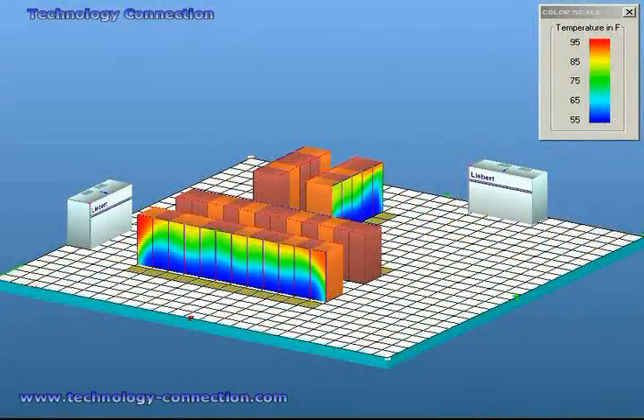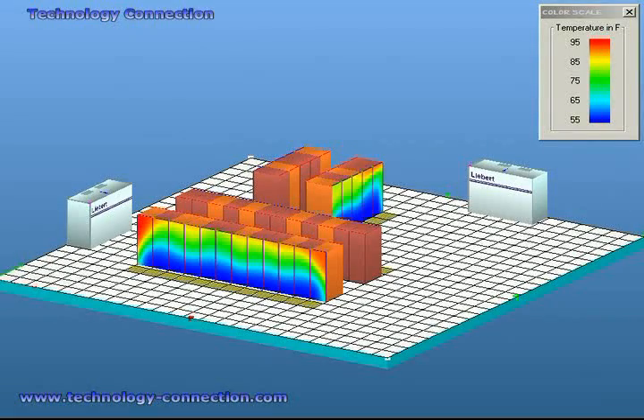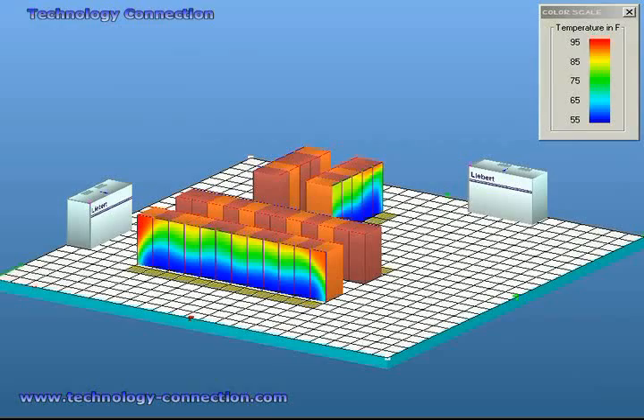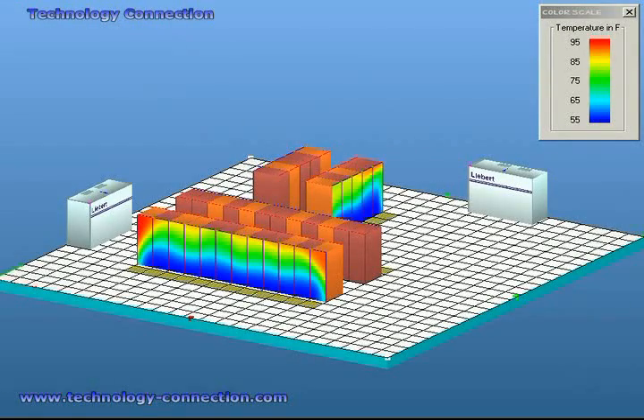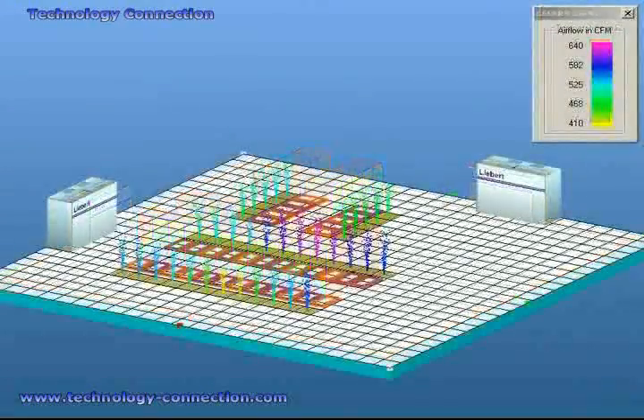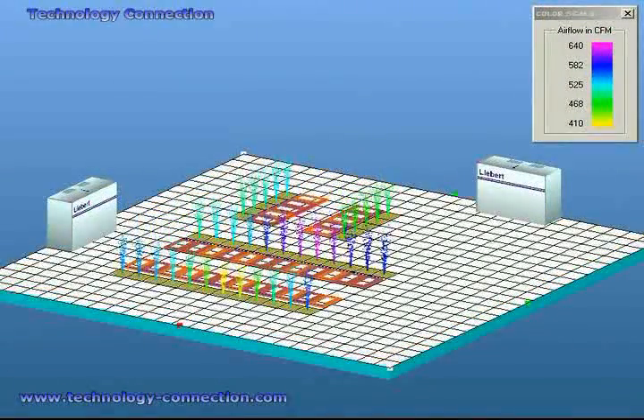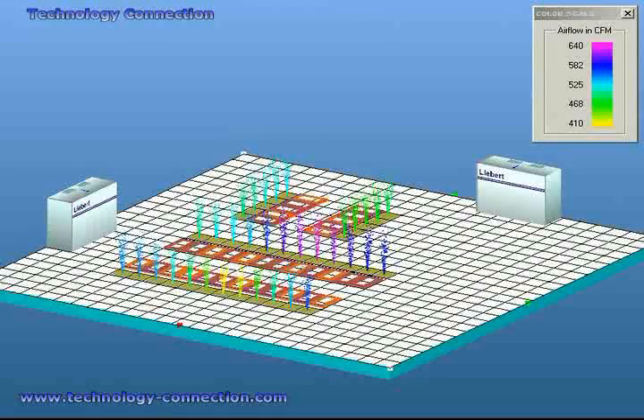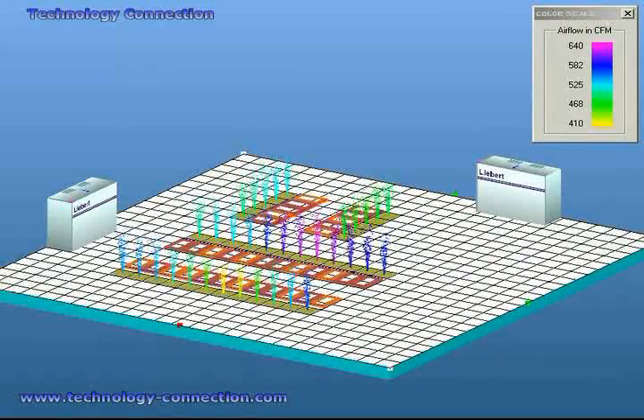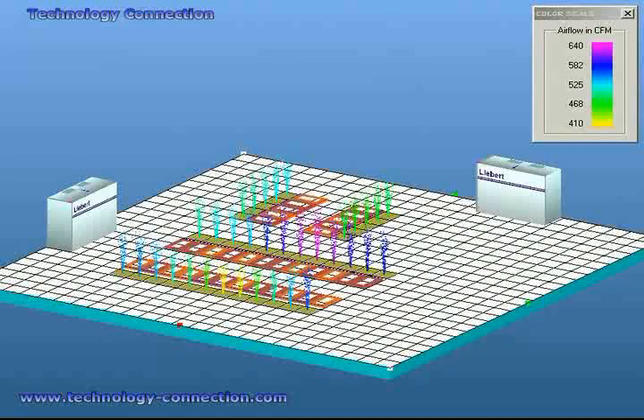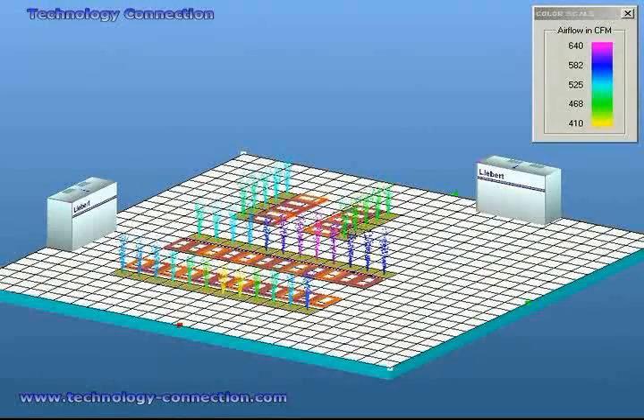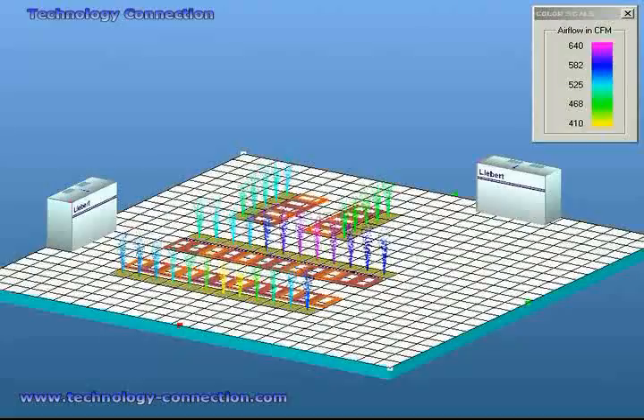Another feature is the ability to detail rack inlet temperatures. From this, we can determine which racks, according to KW requirement, are being properly cooled. With this information, we can run multiple scenarios in which we apply temperature alarms to each server. Not only do we analyze airflow within the ambient room, but the airflow from each perforated tile. It also allows us to determine where, if any, new equipment can and should be placed according to the appropriate airflow required.